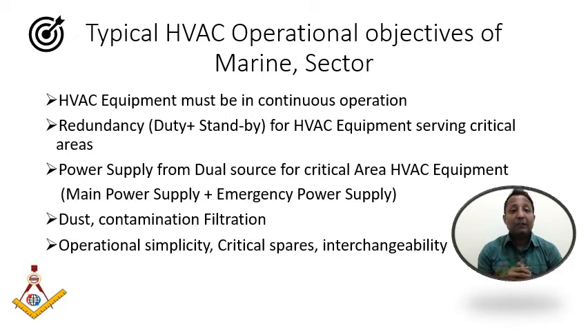Then interchangeability is something - try to select the AHU model, motor model, fan model, or ventilation fan model as similar and close to each other, because if a failure happens to one, the spare parts are common. So you don't have to buy a different capacity motor, because if one spare is there, you can easily interchange with each other. So try to standardize the requirement as soon as possible by being flexible in the design.